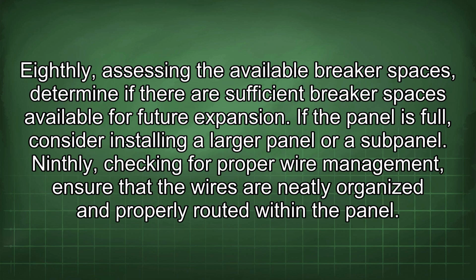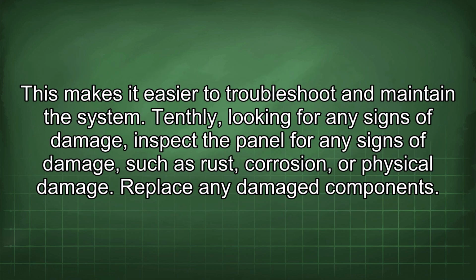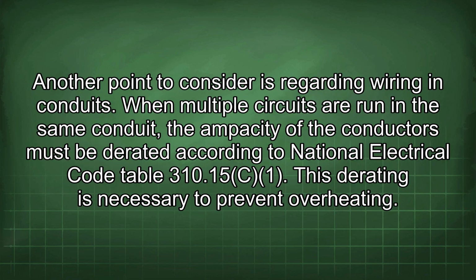Ninthly, checking for proper wire management. Ensure that the wires are neatly organized and properly routed within the panel. This makes it easier to troubleshoot and maintain the system. Tenthly, looking for any signs of damage. Inspect the panel for any signs of damage, such as rust, corrosion, or physical damage. Replace any damaged components. Another point to consider is regarding wiring in conduits.